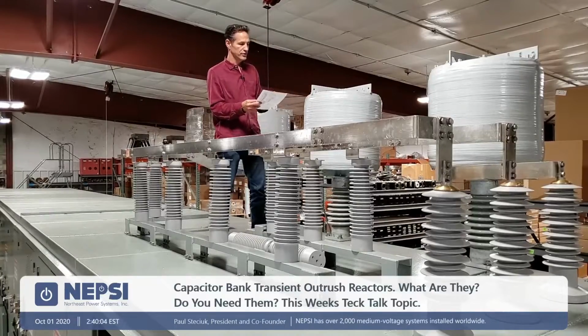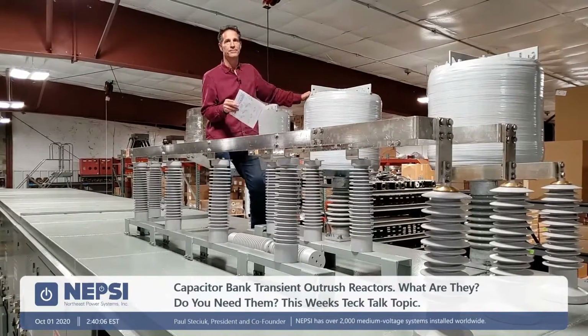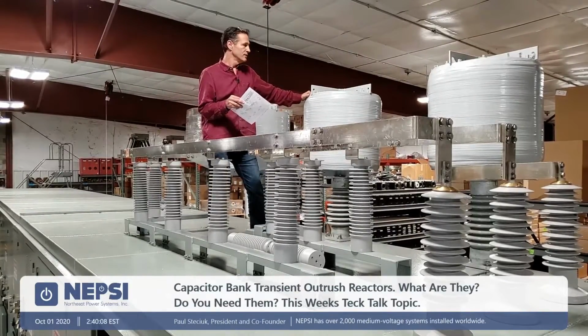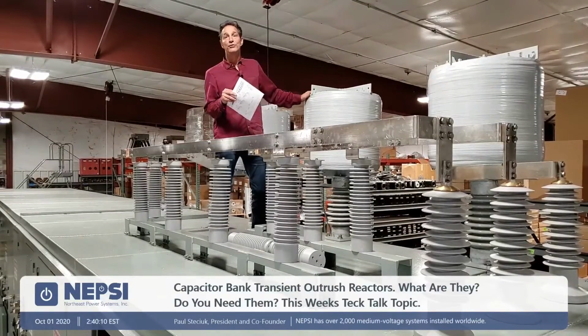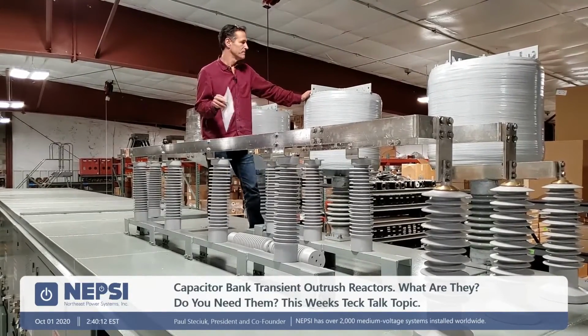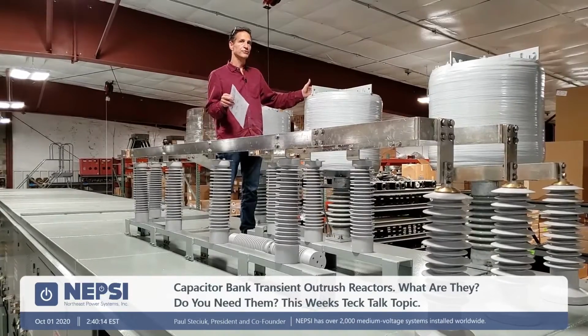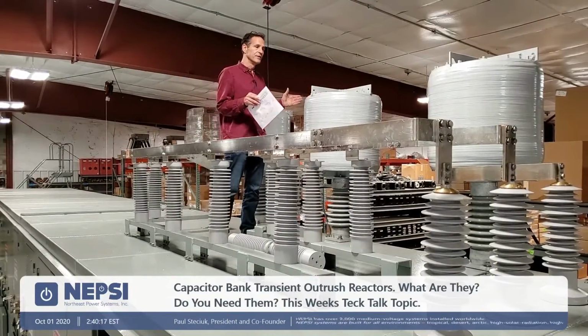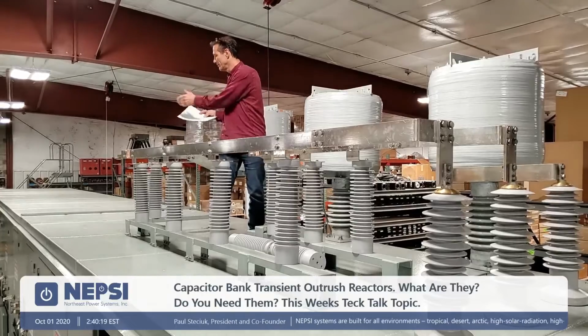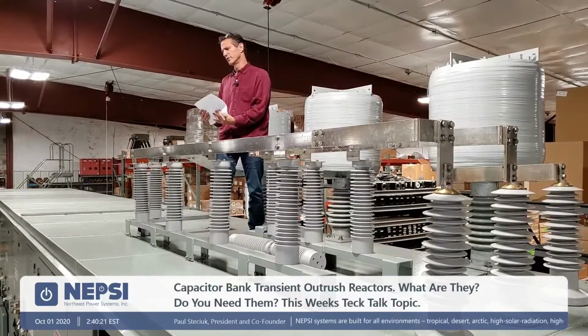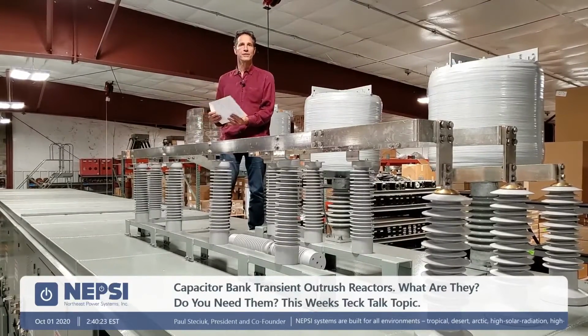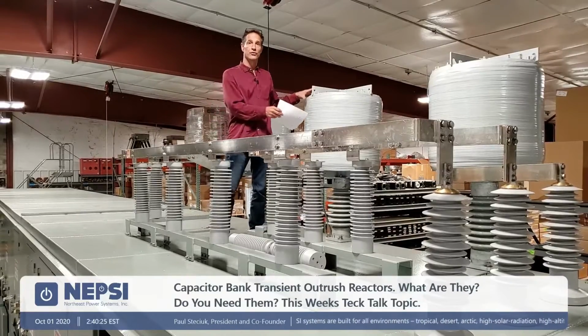So these right here are rated 227 microhenries. Oftentimes you might say 0.227 millihenries, but they're 700 amps, 0.227 millihenries, and they're on the input to this entire 40.5 kV system. So they're the input. So there's a lot of current to it.